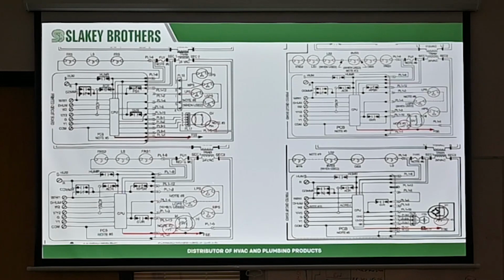This is your low gas pressure switch, if it's even used. Okay, it's your low pressure switch and your high pressure switch. Then on the modulating gas valve, the low gas pressure switch is optional. So there's 3 pressure switches on that one. Low gas pressure switch is optional. Low pressure, high pressure here. And we're not going to worry about this because it's a transducer. That's an ultra low NOx unit.